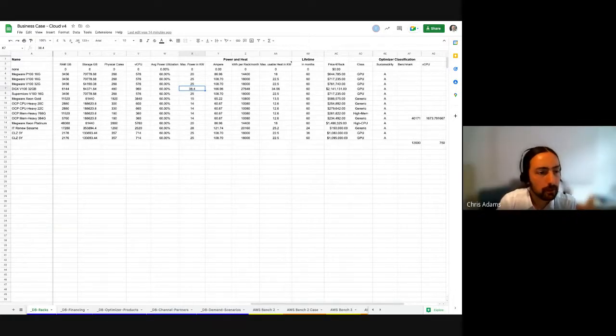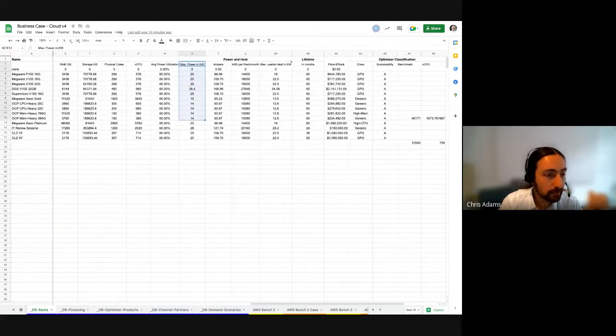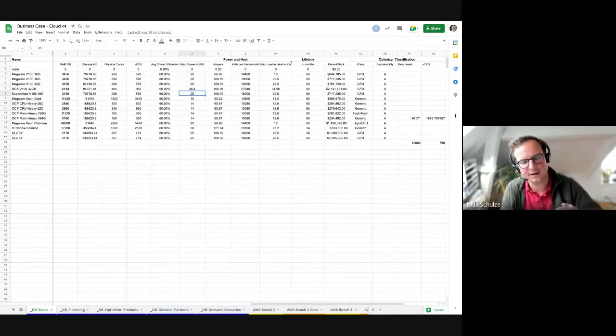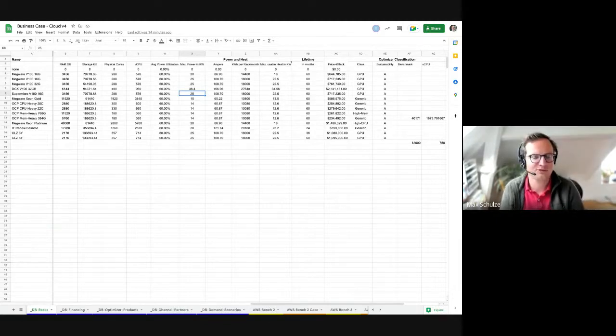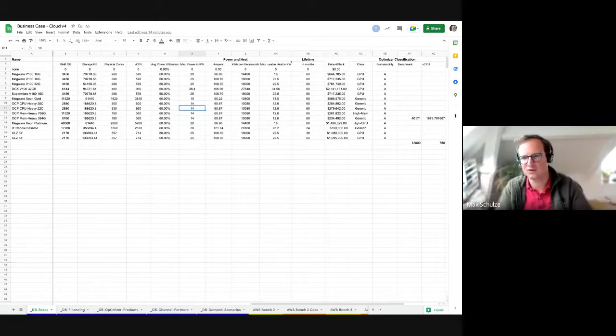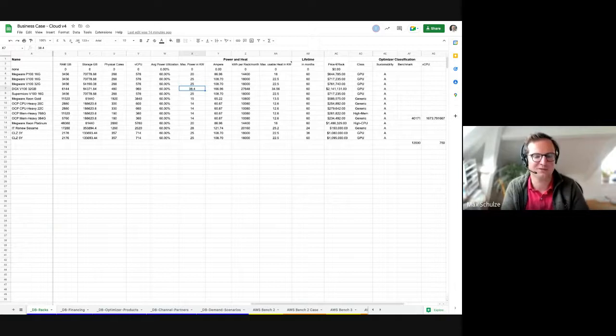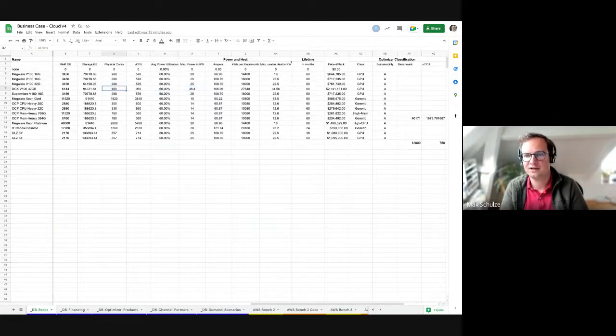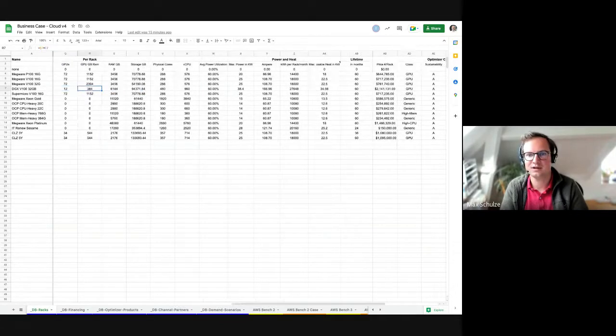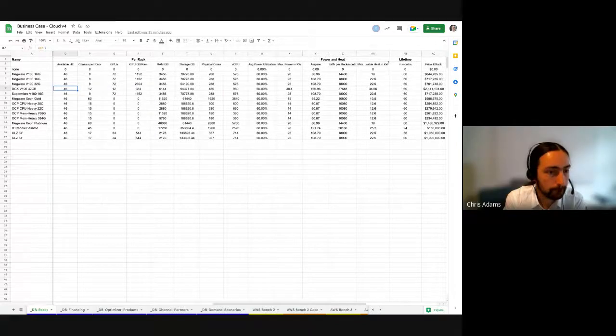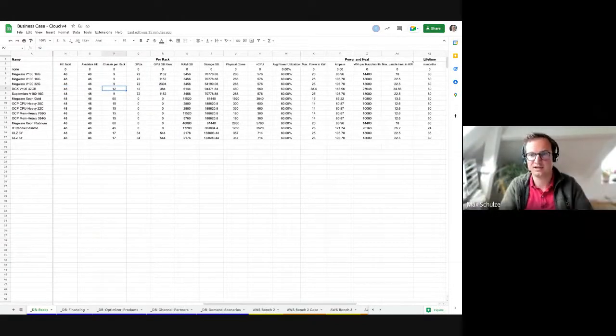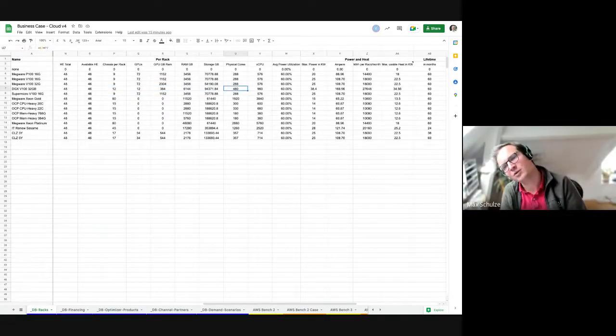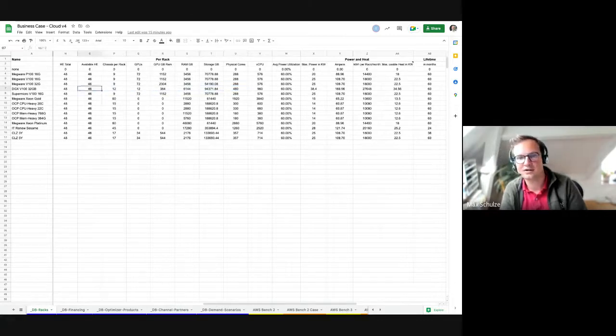A GPU-heavy rack configuration: for example 72 V100 Tesla chips, the power goes up substantially. At a median of perhaps 20 kilowatts of draw per rack, as soon as you're at 40 to 50 racks you're looking at a megawatt automatically. That has implications for the transmission infrastructure beneath the data center. That's another externality not accounted for: society pays for it through grid fees — grid operators have to build high-voltage power lines and new substations, paid for collectively through grid fees.